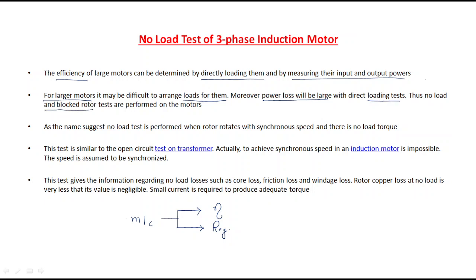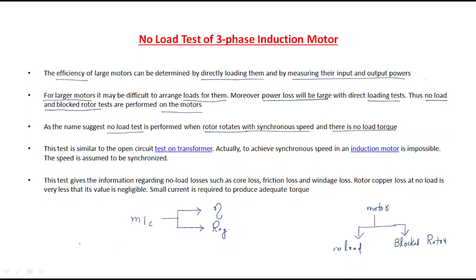To address this, we have two tests: the no-load test and the blocked rotor test. For any motor, these two tests are performed to understand its behavior. The no-load test, as the name suggests, has no load. The blocked rotor test means it is fully loaded. The no-load test is performed when the rotor runs at approximately synchronous speed with no load torque.